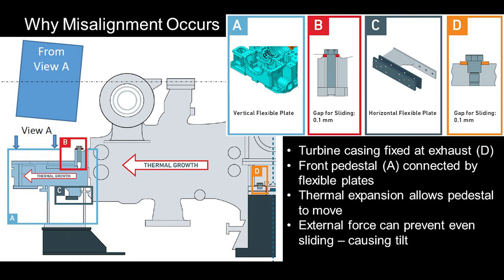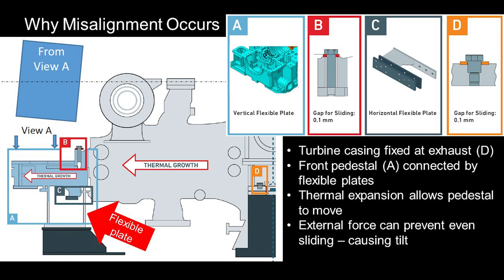So why does this happen? The turbine casing is fixed at the exhaust end, D. The front pedestal A and the lower casing are connected by flexible plates to allow thermal expansion. After operation and during cool down, pedestal A should slide back to its cold position. But an external force prevented it from sliding, causing the pedestal to tilt and misalign.